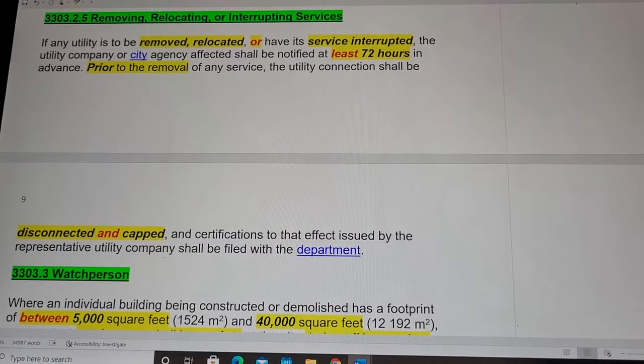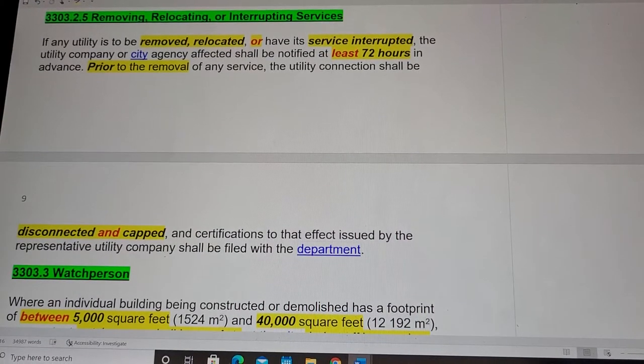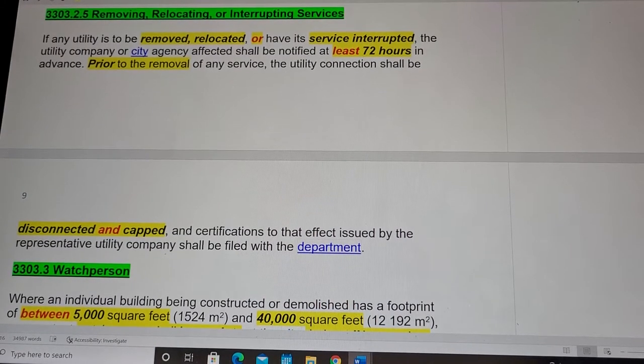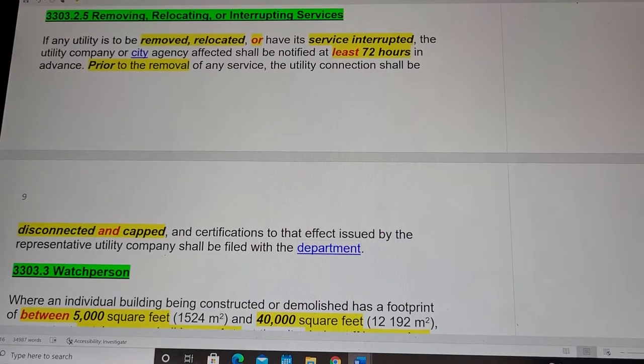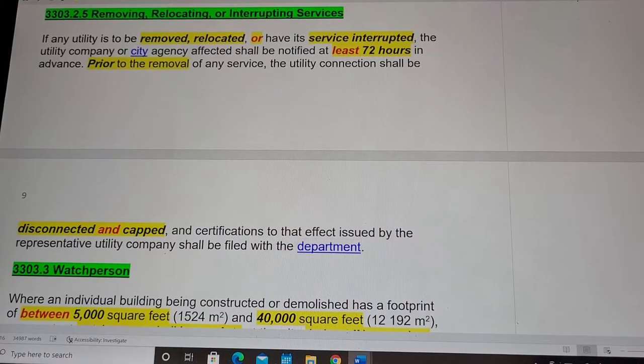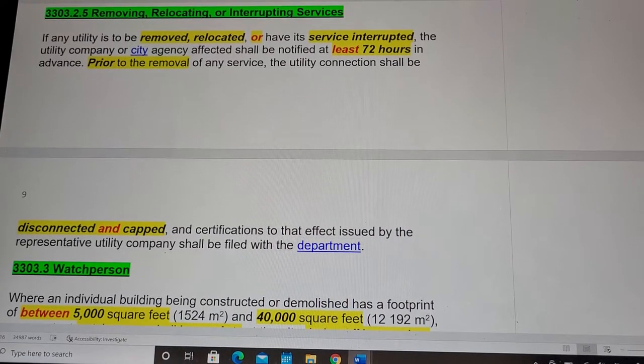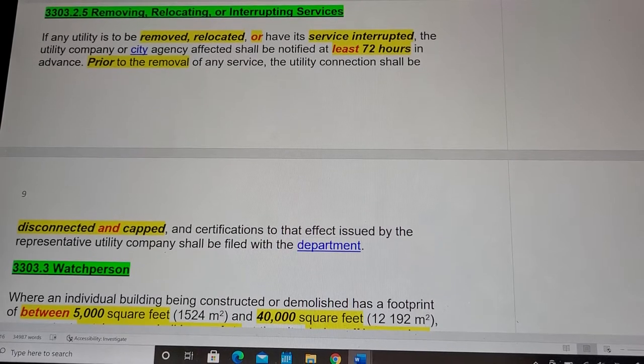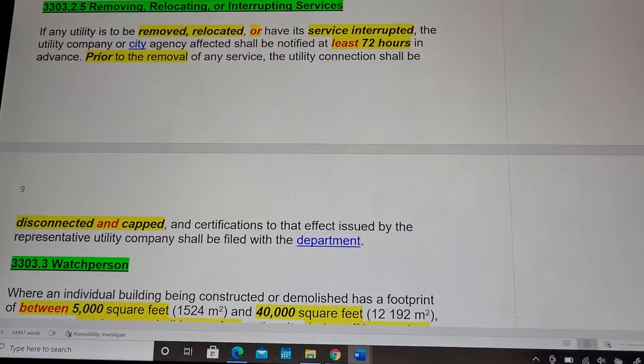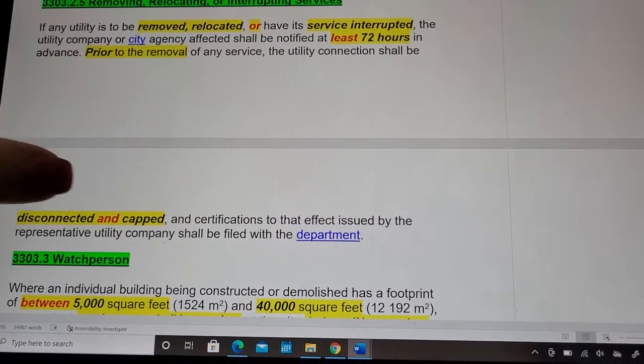If any utility is to be removed, relocated, or have its service interrupted, the utility company or city agency affected shall be notified at least 72 hours in advance. Prior to the removal of any service, the utility connection shall be disconnected and capped.